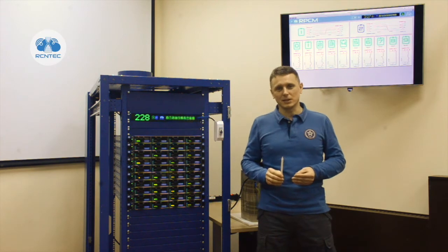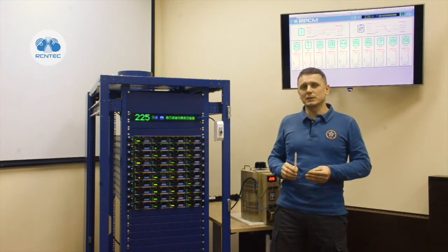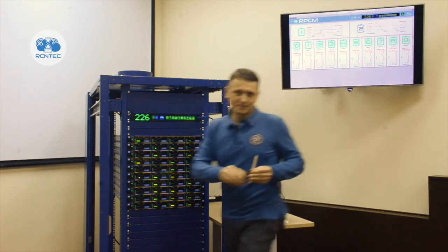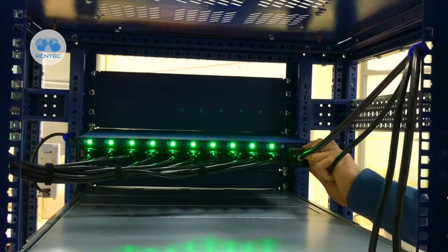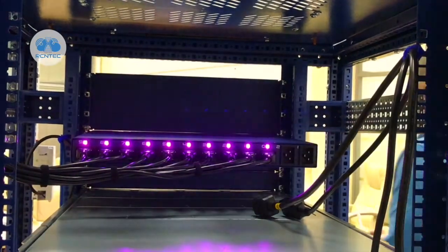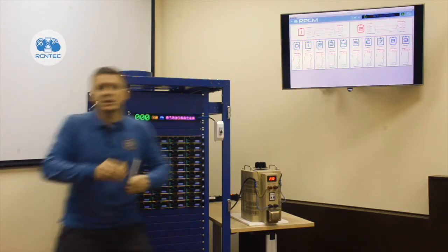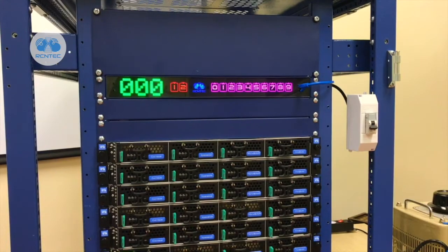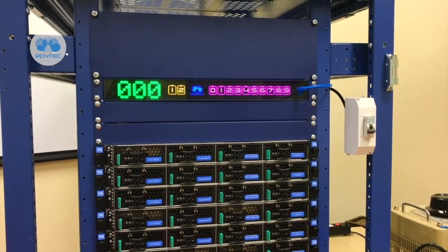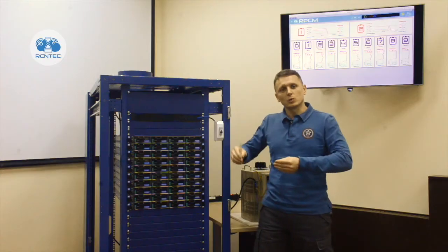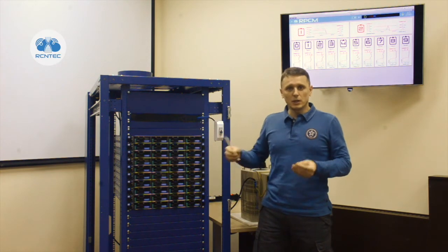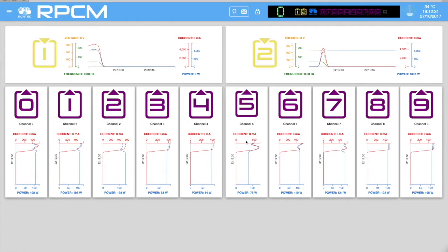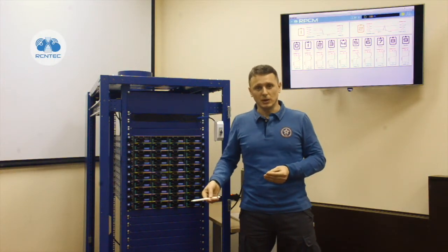But for the most curious, I'll now demonstrate what will happen if we turn off both power supply sources. From the consumer's point of view, there's nothing surprising. They've all lost power. But during a 10-second span, RPCM will save information about that event. And in the future, after RPCM is turned on again, you'll be able to understand what happened at the moment the module was turned off. It also allows for notifying external monitoring systems and administrators if the network is still capable of transmitting data.